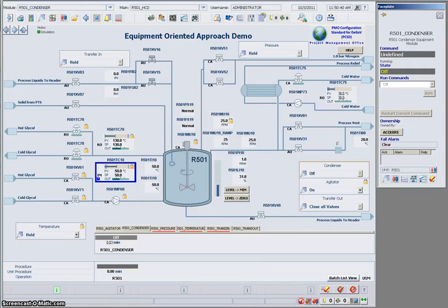Applying some human-centric design techniques, we can develop better graphics that are easier for the operator to identify the important elements. The basic theory behind that is to develop graphics that during the normal state are very muted. As you can see from this example graphic, we've used shades of blue to indicate all of the normal states. Blue is a good choice of color, but you can also use shades of tan, shades of gray, anything that fades into the background. If the operator needs information, they can detect it very easily from the screen.